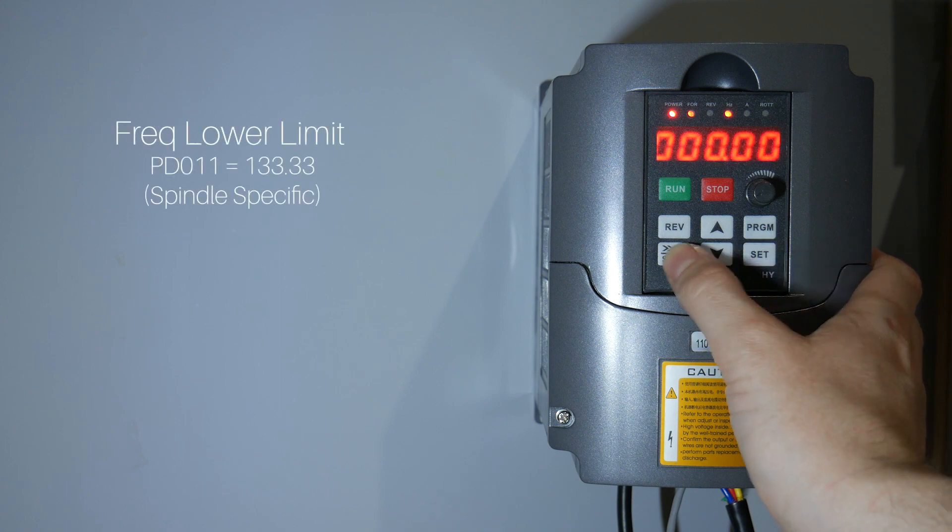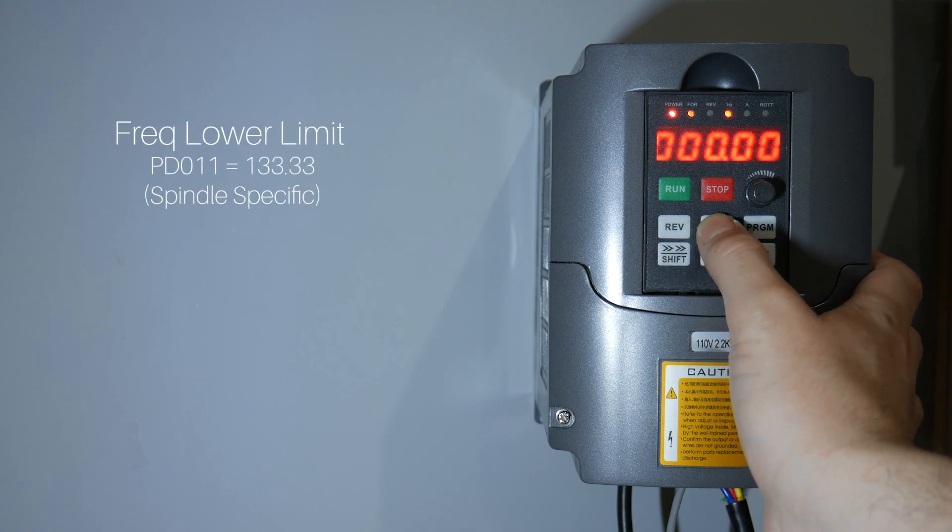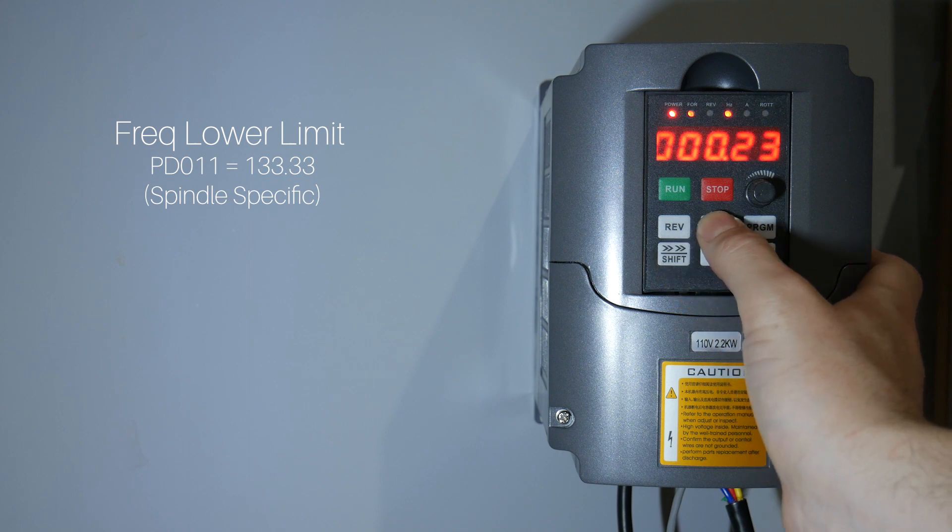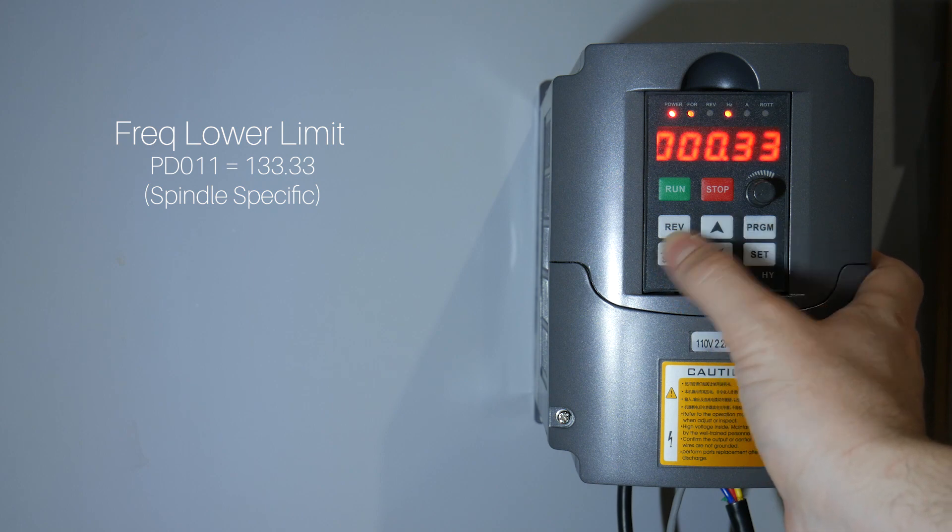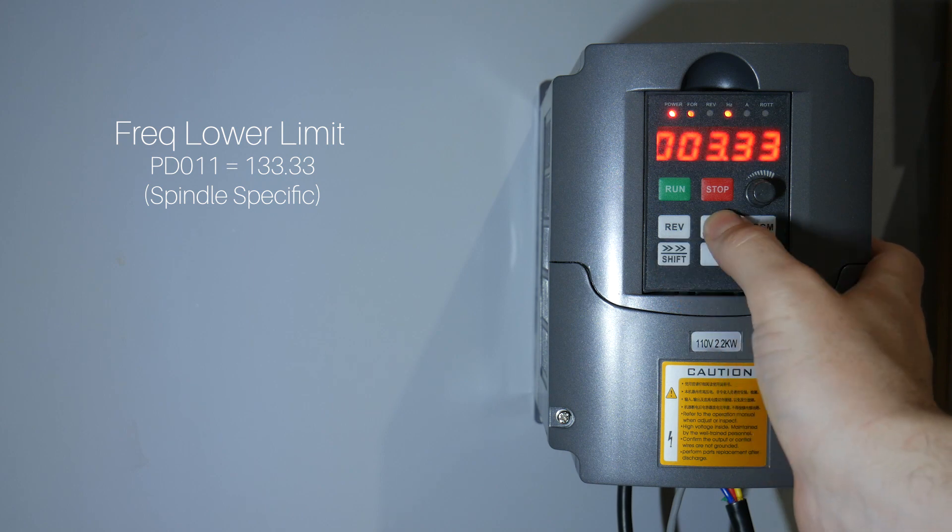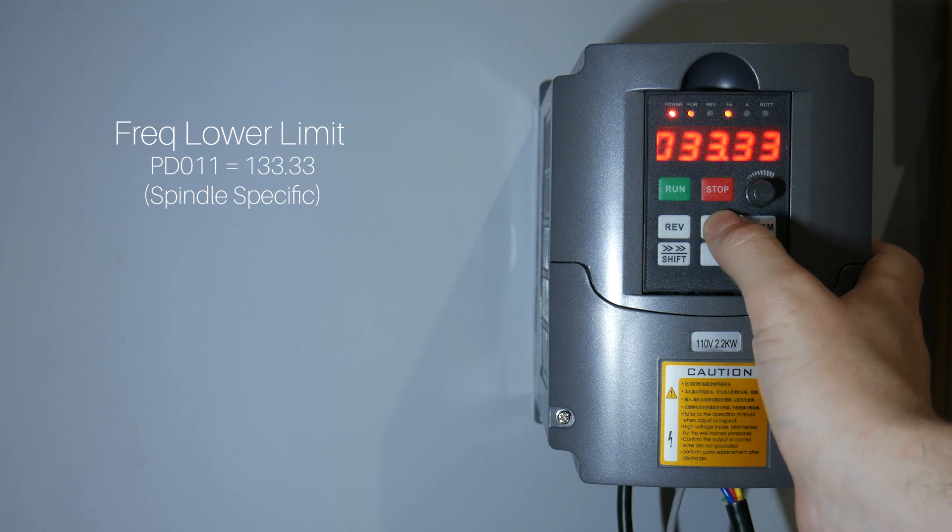Frequency lower limits. Set this to 133.33 hertz for 8000 rpm. This is setting the lowest speed the VFD will allow.